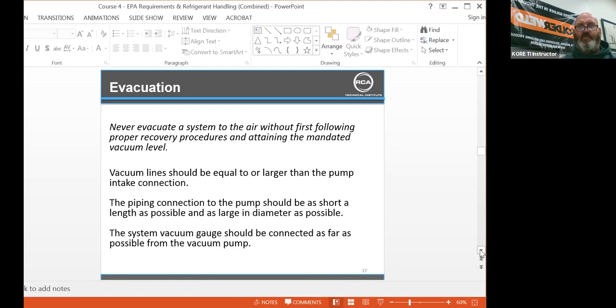I used to do a lot of built-up work on 60 tons, 100 tons, 200 ton built-ups. We would actually braze in at the evaporator coil an access port and attach the micron gauge there. And then our vacuum pump would be on the roof and it could be 40, 50, 60, 100 feet away. It would take longer, but we knew that if we had a really low level under 500 microns out at the evaporator coil, that we were definitely in a good spot.